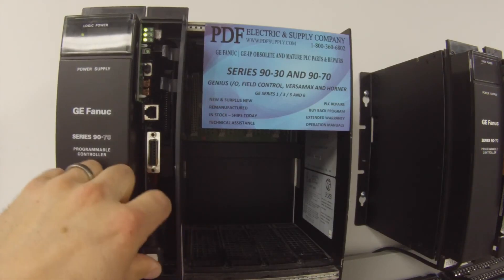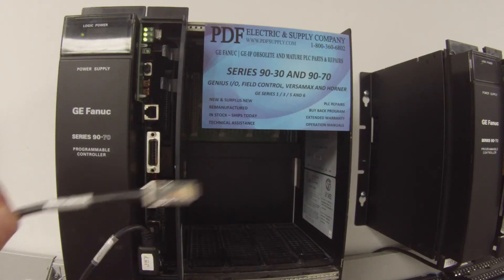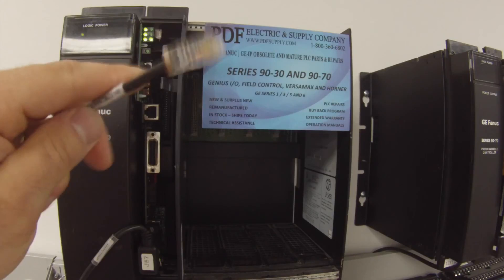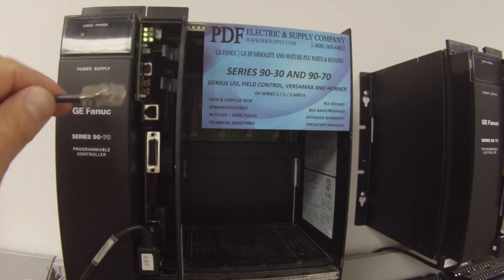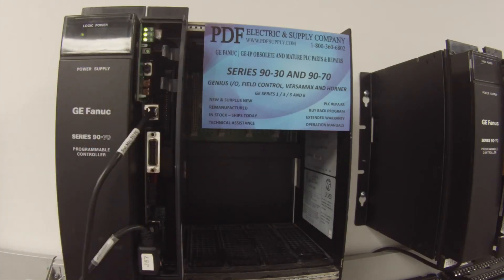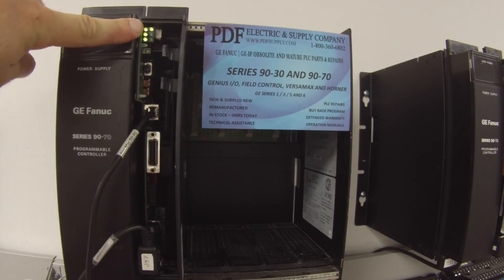The last one uses a different cable — it's a little bit more special. I have a part number here: IC693CBL316. It looks like a phone jack on one side and on the other side is a serial connection that's going to go to my computer. I'm going to go ahead and plug that in on the back of the computer. When I do, I should have communication on port number one — a blinking LED. And I do. So that's a complete test.